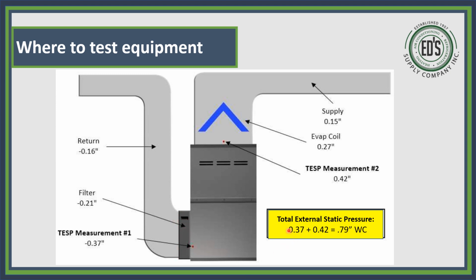Now, you see these numbers, they got 0.37. That was your return. Even though you have a negative, it will be a negative number sometimes because that's a return. Okay, so keep that in mind. But we're not going to use it as subtraction. We're going to add it. So you take the supply, 0.42, you add it to the 0.37, and you get a total static pressure of 0.79, or you'd round it up to 0.80.